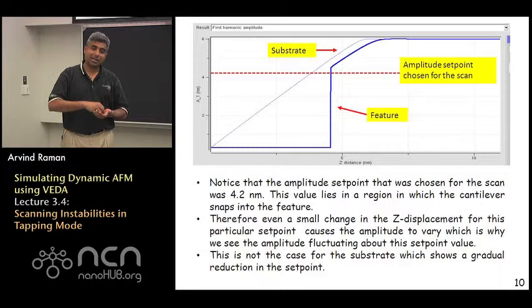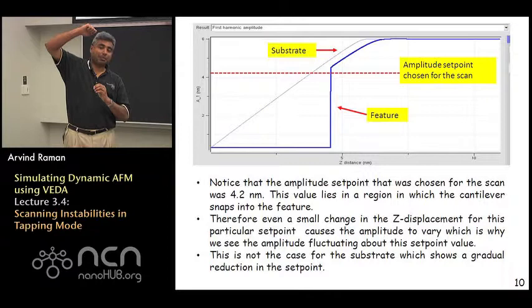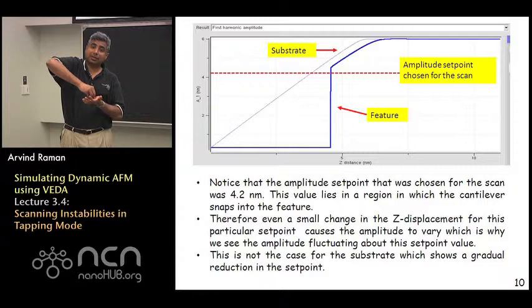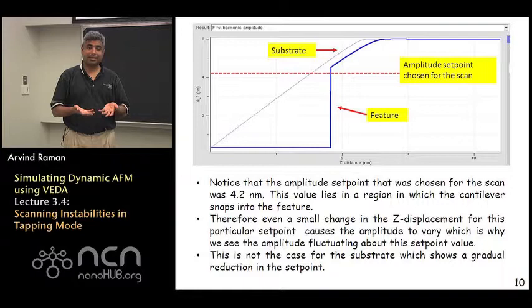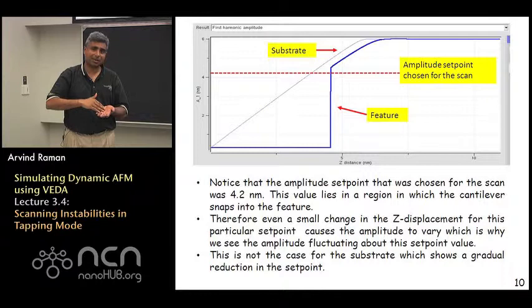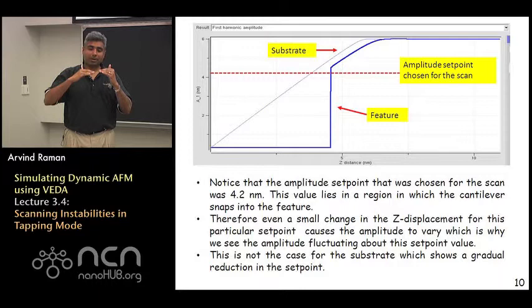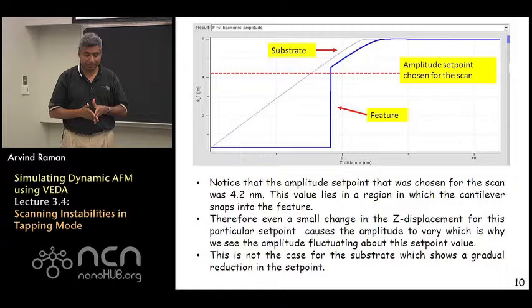So what happens in this case is the controller is trying to do is as you are scanning over the feature, the tip snaps into the sample so the amplitude decreases to zero, but we want an amplitude of 0.7 times the free amplitude, so the controller moves the z piezo as a backup to try and get to that amplitude and the tip is still stuck to the sample and it keeps the base of the cantilever z moving up until it snaps out. When it does snap out the amplitude becomes more than 70 percent set point, so the controller then tries to move it back down to try to get to this 70 percent set point, but if it comes any close it is going to snap into the sample. And so by choosing a 70 percent set point we are at the point where we cannot have stable oscillations. The tip is just going to snap into the sample. So the 70 percent set point is not achievable in the context of this material that you are going to try and scan.